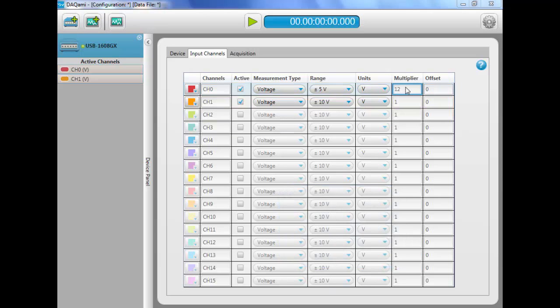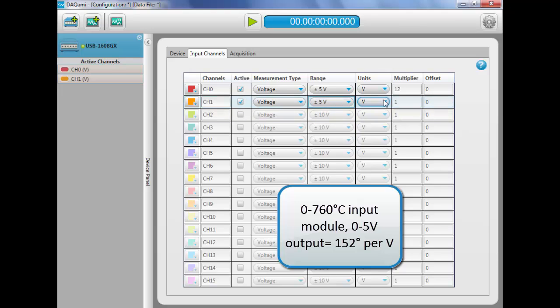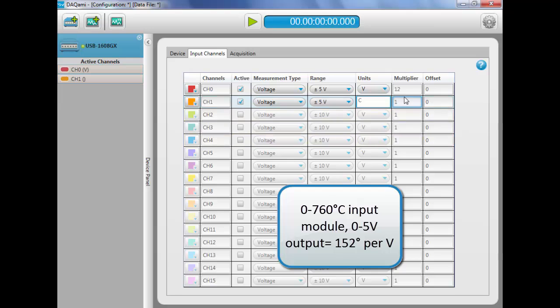For channel 1, we have a 0-760 degrees Celsius thermocouple input module with a 0-5 volt output, or 152 degrees Celsius per volt. So we'll enter a multiplier of 152.